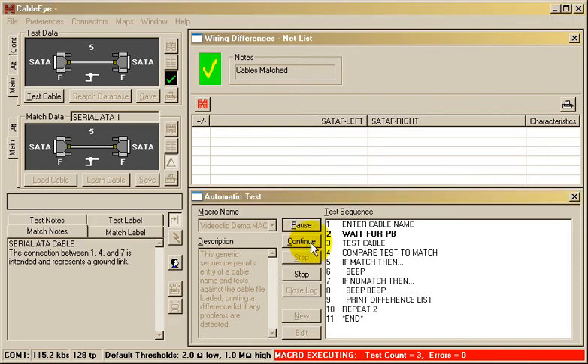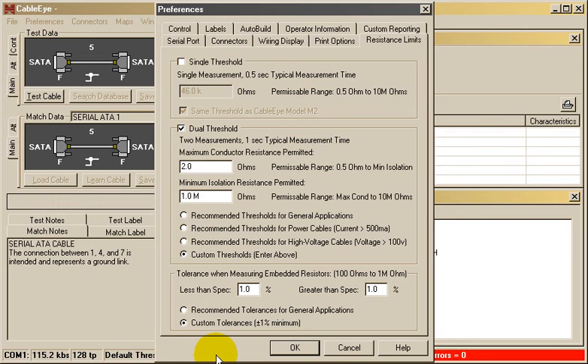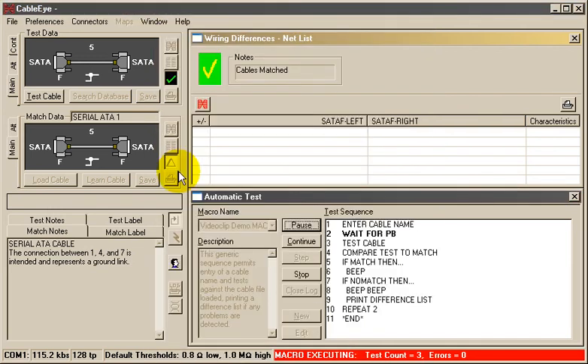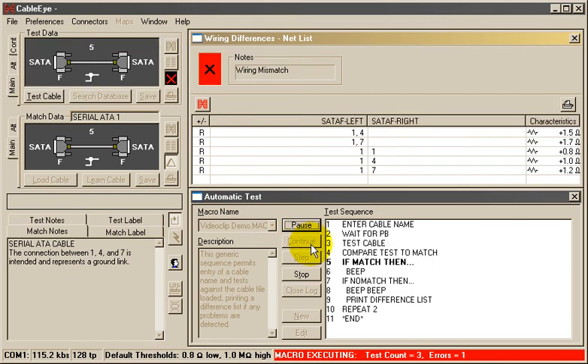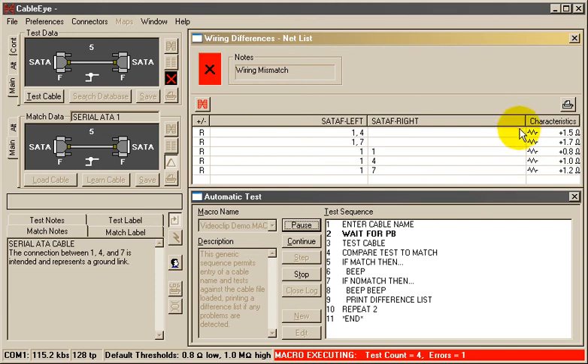To simulate a failure, I'm going to lower the default threshold to a point that I know is not acceptable for this cable. Now, I'll press the button to test. A failure occurred, a report is being printed, and you can see here a list of the conductors whose resistance failed the threshold.